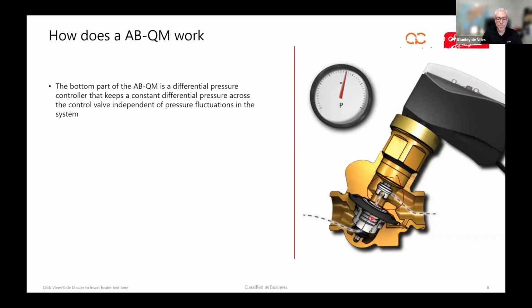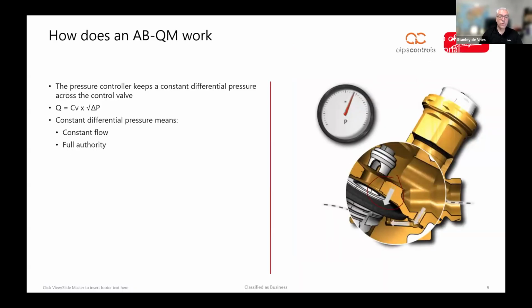My understanding is that all of you are control contractors, so I guess you can understand what that means. But just to lay it out a bit more, the flow through a valve is determined by the differential pressure and the CV value, and the CV value is basically the size of this hole.